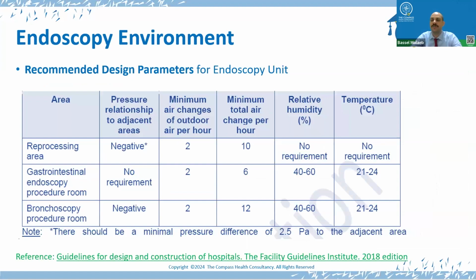So each area within the endoscopy unit should have a designated flow for the safe physical movement of dirty scopes that do not cross-contaminate with the clean scopes, which will come out of the cleaning process and will go to the storage area. This table represents the design parameters, and as you can see, we need to be ensuring in the reprocessing area we have negative pressure. The minimum air changes per hour should be 10. In addition to the procedure room, there is no requirement to have negative pressure, it's equal pressure. And a bronchoscopy procedure room, where it's considered as an airborne isolation room, should have negative pressure with 12 air changes per hour.